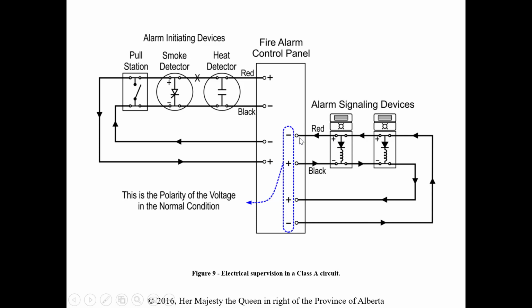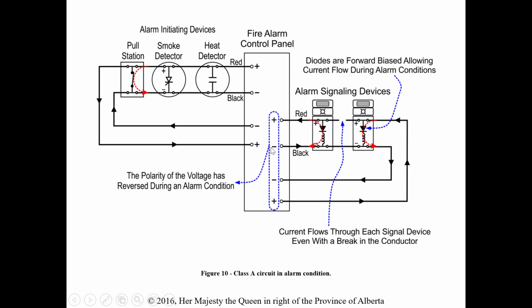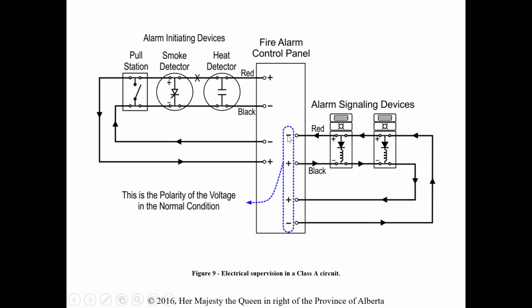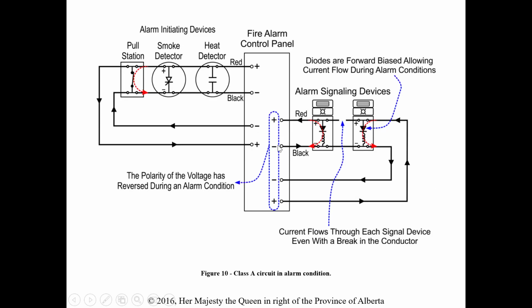The same thing is going to happen in the signaling circuit. We're going to loop back to the panel, so we don't have any end-of-line resistors here either. That's a Class A, where we don't have end-of-line resistors. Now again, when we go into a signaling scenario, where a pull station or a detector has been activated, the same thing is going to happen with the polarity in the signaling circuit. Here's what we would see in a normal state. The polarity here is the same, but on our device signaling circuit, this was negative and this was positive. Now this is positive and this is negative. So the panel switches the polarity going to the signaling device.